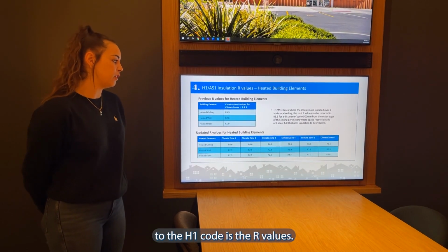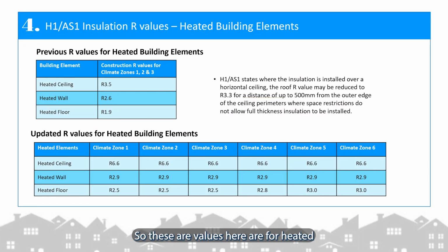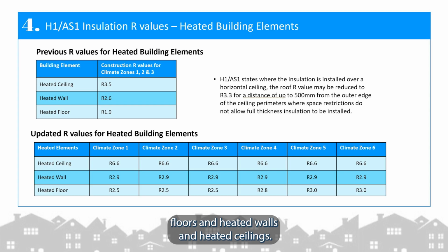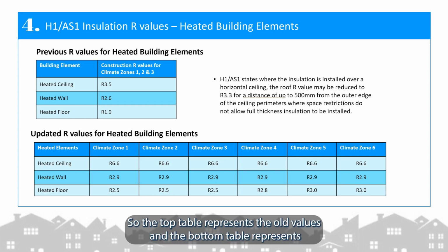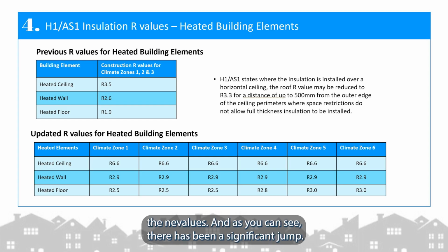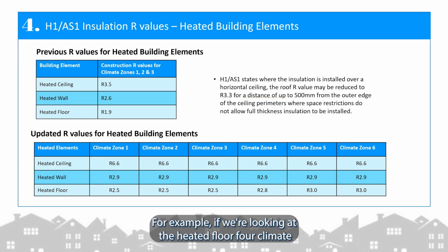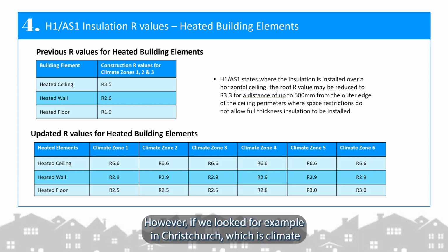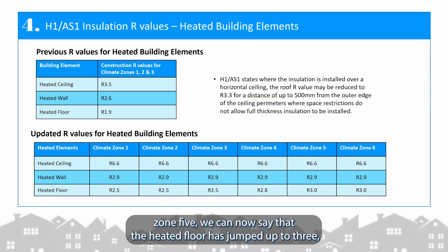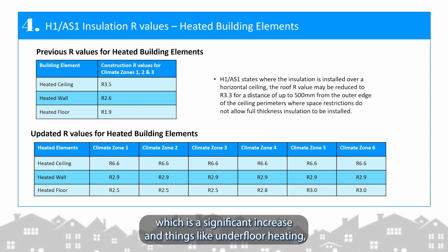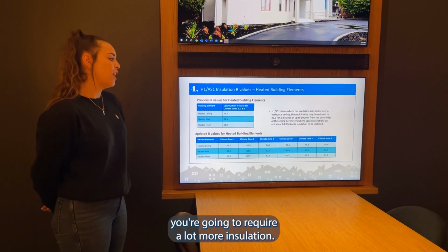And one of the major changes to the H1 code is the R values. So these R values here are for heated floors and heated walls and heated ceilings. So the top table represents the old R values and the bottom table represents the new R values. And as you can see, there has been a significant jump. For example, if we look at the heated floor, for climate zone 1, 2 and 3 in the old code it was 1.9. However, if we look, for example, in Christchurch, which is climate zone 5, we can now see that heated floor has jumped up to 3, which is a significant increase in things like underfloor heating, and you're going to require a lot more insulation. So definitely something to be aware of.